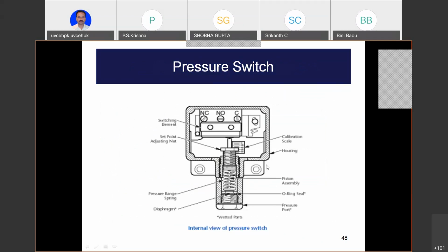Now, I don't think I'm going to only tell you this and close shop, because the design is all given there. Now, this is a pressure switch, and it operates in a manner like this. You know that plant we designed, that plant has got 3 pressure switches. Let us say we take one pressure switch. You push ethylene oxide vapor, or whatever reactor vapor, in that, and then what happened? Here you've got the sensing element. Here there's a seal, there's a piston, and it moves inside the chamber, tight piston, and that triggers the micro switch. And when the micro switch is triggered, the switch is operated. So we designed the switch such that when the switch is operated, that is when the contact is closed, it is healthy.